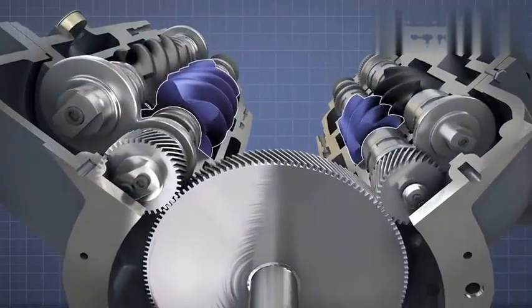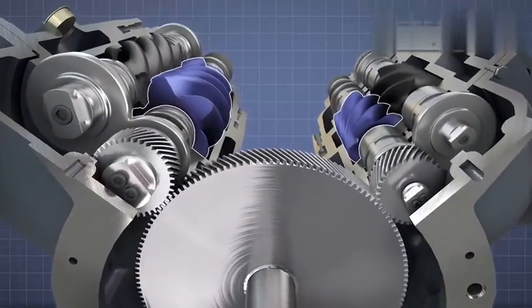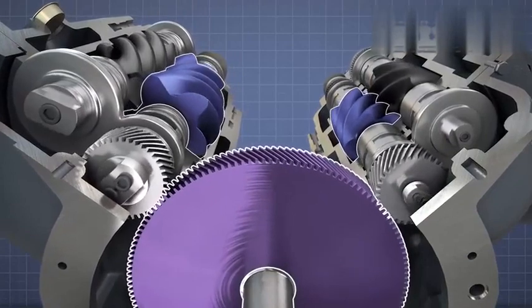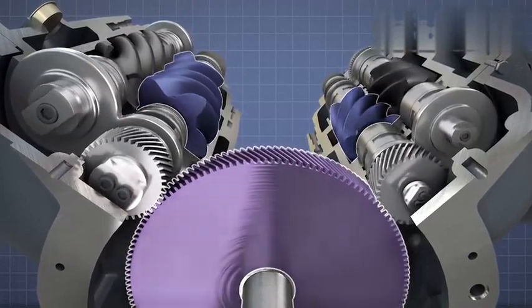The male rotors of both the first and second stages are driven by a single main gear at the back of the air end. Helical timing gears at the front of both sets of rotors ensure perfect synchronization is kept between the rotor pairs at all times.